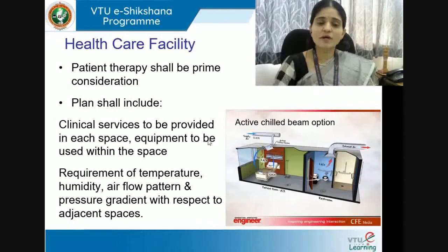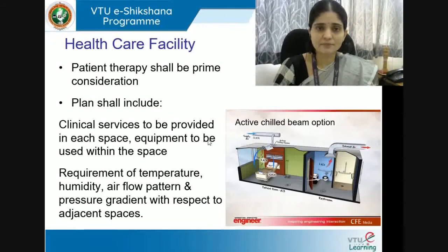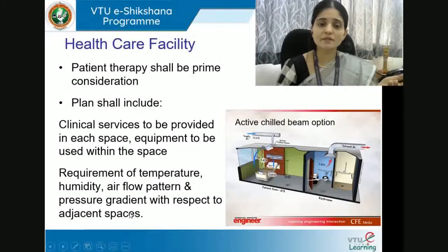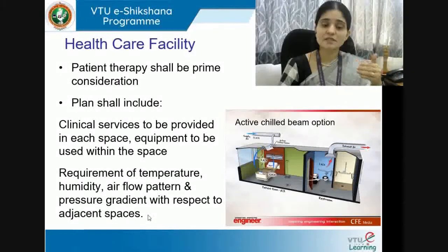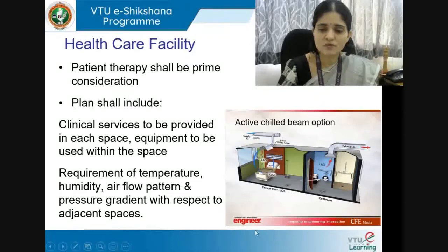Secondly, the requirements of temperature, humidity, airflow pattern, and pressure gradient with respect to adjacent spaces must be determined. We can have two types of pressure — positive and negative — and knowing where to operate each and at what degree is essential. Air changes per hour must be decided for each space, along with temperature and humidity, which are the major criteria of air conditioning. Looking at the airflow pattern and ventilation aspect, there are various options such as the active chilled beam option sourced from service providers.